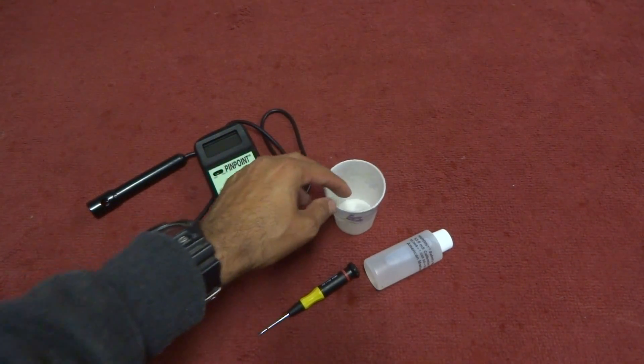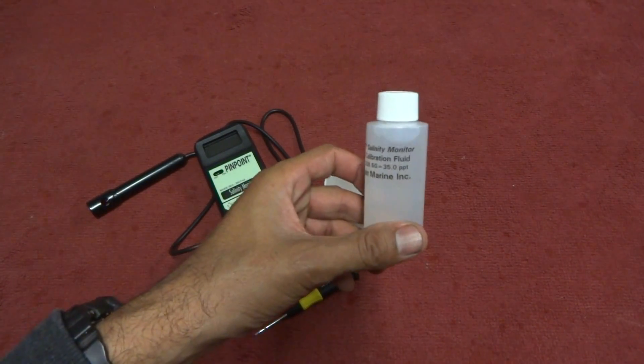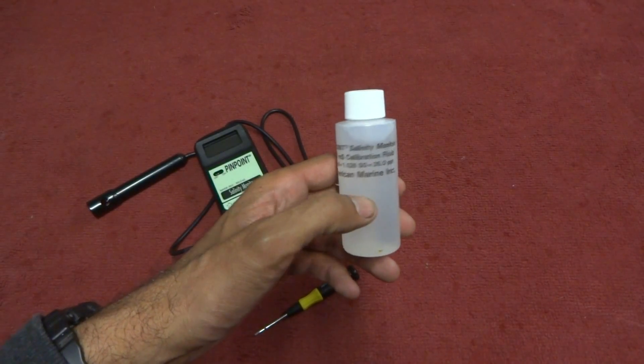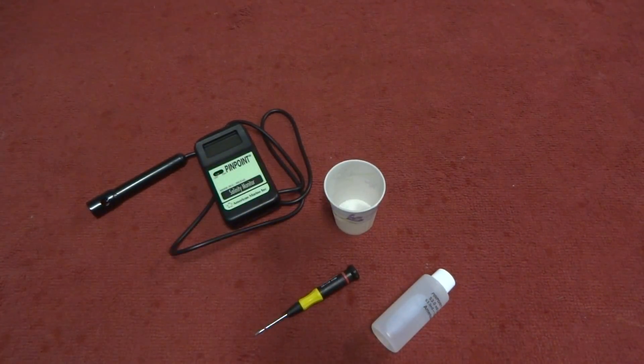In my case I'm using a paper cup and the probe for the salinity monitor itself. This salinity calibration fluid can be reused so long as it's not contaminated by any other liquids and so long as you're using a clean container.